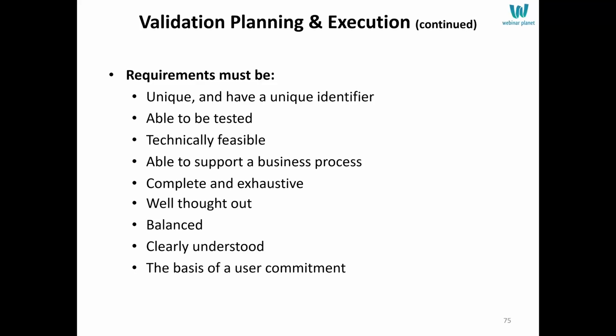Requirements have to be unique, uniquely identified, testable, feasible, supporting your process. Now, basically, the important thing here is when someone does an action on a system, they expect a response to be a certain way. That's your requirement. I do this, I expect this response. That's a requirement. Got to be clearly understood between whoever is developing the software, testing it, and who is using the software in the end, because it's the basis of a user commitment.